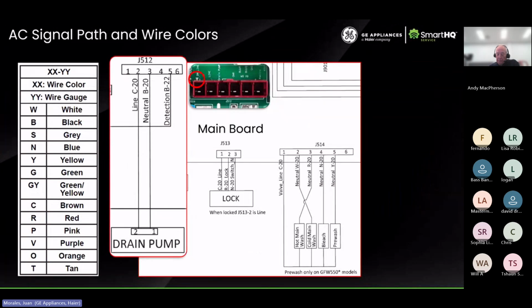Now, your wires are labeled with a letter and a number. The letter is the color, and the number is the wire gauge. If you look at pin number 2 on connector J512, it says C20. C, on the table, is brown, so once we see a C, we know it's a brown cable. B, which is your neutral, is black according to the table. So I'm looking for a brown and a black wire coming from that connector going to my drain pump.